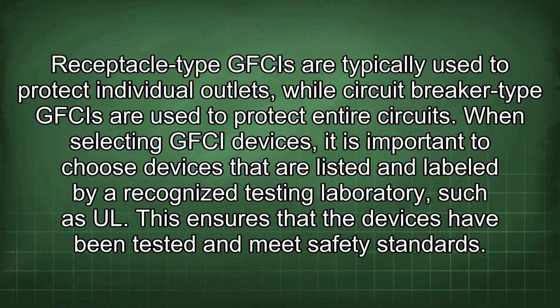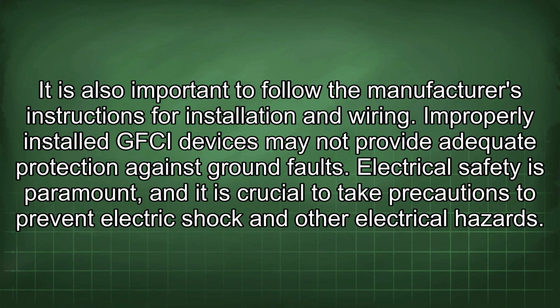When selecting GFCI devices, it is important to choose devices that are listed and labeled by a recognized testing laboratory, such as UL. This ensures that the devices have been tested and meet safety standards. It is also important to follow the manufacturer's instructions for installation and wiring. Improperly installed GFCI devices may not provide adequate protection against ground faults.